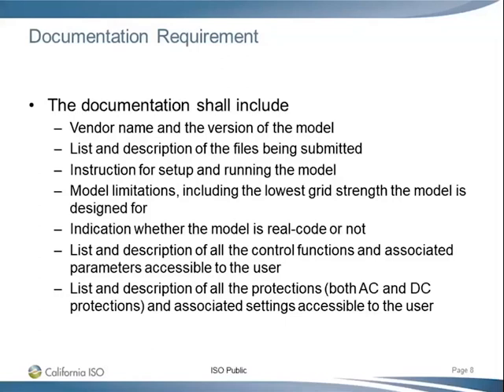Then the list and description of the files being submitted. It should include the instructions for setting up and running the model. So for any particular requirement, such as a library we need to link, you should provide clear instructions. Any model limitations: you should clearly indicate the lowest grid strength this model is designed for. We don't have a requirement on what grid strength the model should handle, but we want to know the limitation of your model. If it's a short circuit ratio of 1, then put 1. If it's 2, it's 2. We just want you to tell us what that limit is. And also tell us if the model is real code or not, since they are all black boxes. We don't know what's inside.